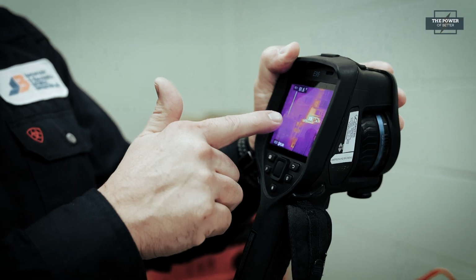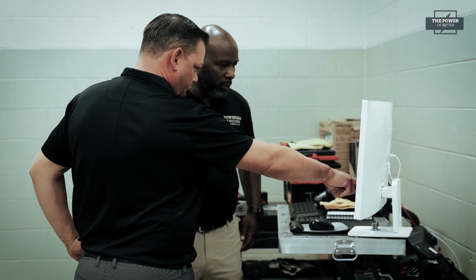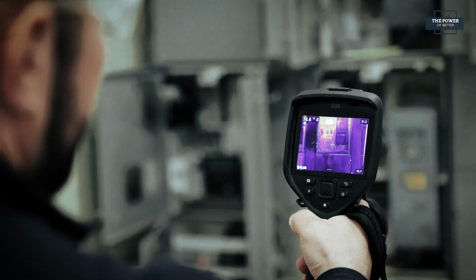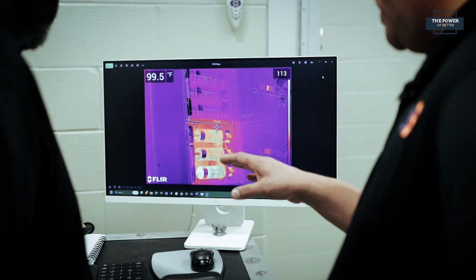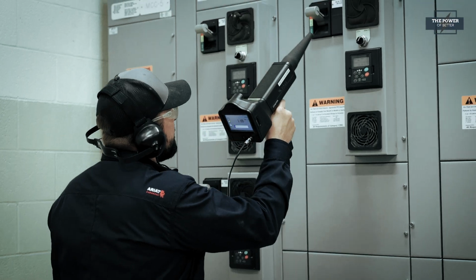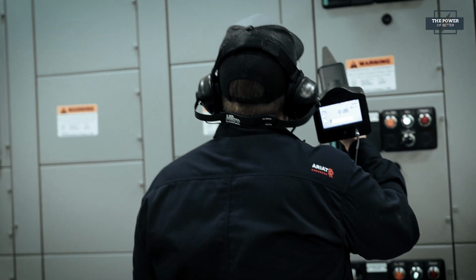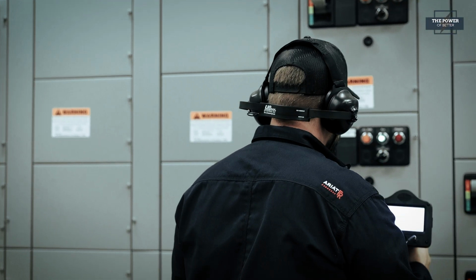Jamerson and Bauwens also used its infrared and other technologies, going to each electrical room, scanning for hotspots and unbalanced loads. So our guys are using not just infrared technology, we're also using ultrasonic technology. Before we even open up the panels, our guys are scanning them to make sure that if there's any anomalies behind the panels, they're listening for it. So the safety for our guys is imperative.